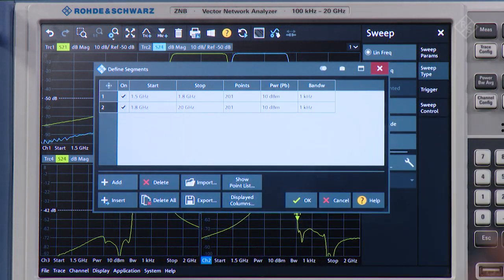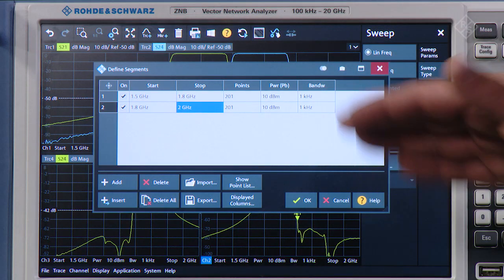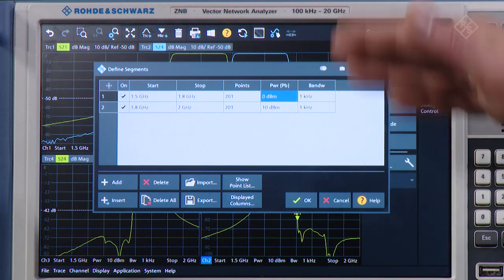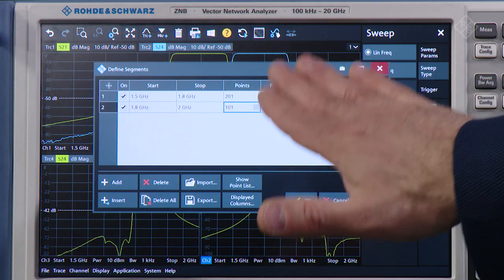I will add another segment and select the stop frequency to 2 GHz. For the bandpass region, I would like to look at the ripple, so we'll keep the number of points to 201. Because I'm in the bandpass, I'd like to prevent compression to my receivers, so I would lower the power to 0 dBm and keep the bandwidth at 1 kHz. For the band reject regions, I don't need so many points, so I will select 101 points, which gives enough resolution. I will keep the power at 10 dBm to maximize my signal-to-noise ratio.